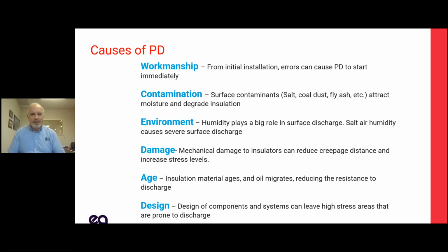Mechanical damage, well, we're in the U.S., people tend to shoot insulators for fun. But any kind of mechanical damage to overhead insulators or any kind of insulation, which is going to change the electric field distribution, can cause discharge. Age is not a big factor. You tend to think that partial discharge occurs already. Well, it occurs the whole time. It may not lead to failure until 30, 40 years down the road. But as things get old, oil migrates out of PILC cables, and over time, insulation can dry out. So age is a minor factor.